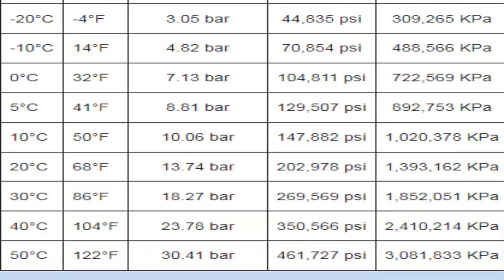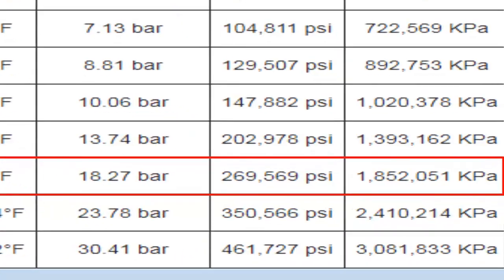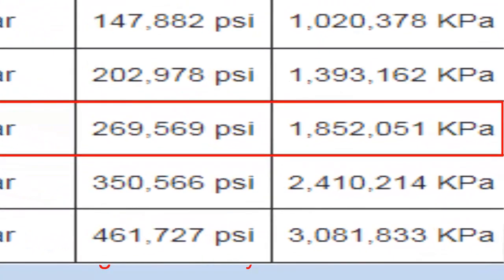When the equipment is off and the pressures are leveled — both the low and the high — they have the same value. We are going to have a pressure close to 260 to 265 PSI.